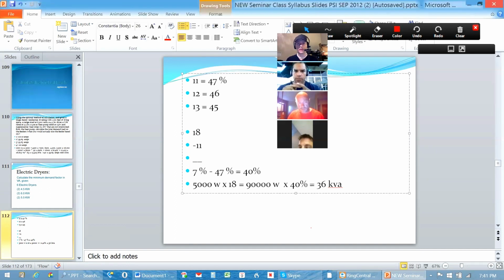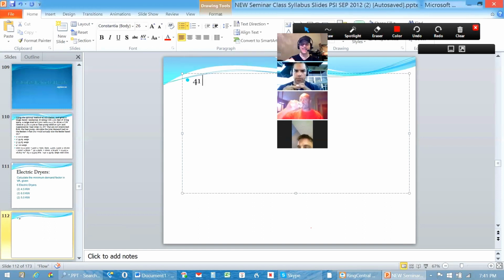Now, just to be covered, as another example, I'm going to do the one that was 41 dryers. At 41 dryers, the only thing that changes is that instead of a 1% derate for each additional one, they've already lowered that number through the process of 1 through 23. So when I get to 24 to 42, I'm just taking 0.5% for anything above 23. So if I had 41 dryers, I would take 41 and subtract 23 from that number. And again, I'm on that second line there on Table 220.54. That would give me a balance of 18 additional dryers.